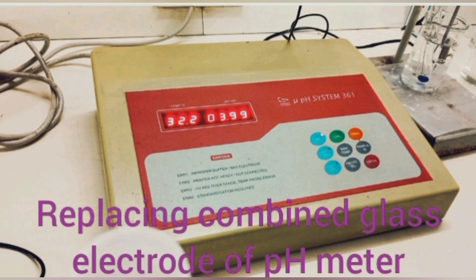If it is not working, then try to replace it with a new glass electrode. Many models of the machine have different glass electrodes. Nowadays iron and plastic electrodes are also available in the market, but for better viewing and good accuracy of the result, it is advisable to use a glass electrode only, especially for pH meters in commercial industries as well as in commercial laboratories. I recommend this glass electrode because it is very easy to wash, however difficult to maintain and handle.